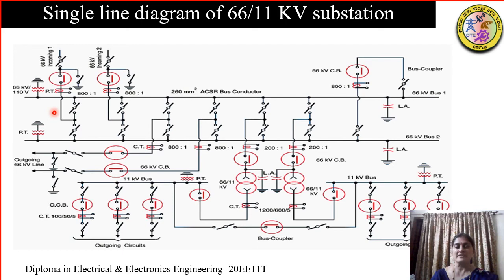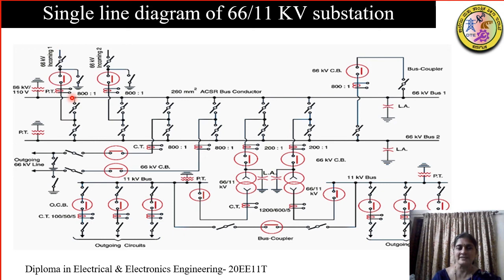We have already studied the different components of a substation. Now we are going to put all these components together to draw a single line diagram. In this line diagram, we can see that there are two incoming lines and two bus bars. The incoming lines are connected through an isolator and a circuit breaker. We also have a double break isolator here, a PT, and an earthing switch.